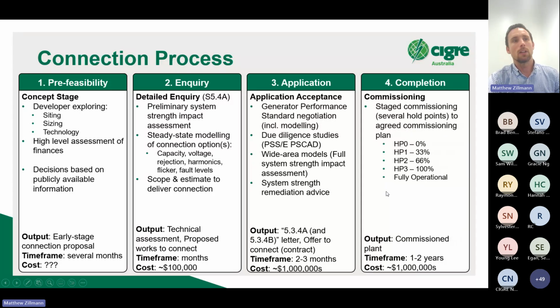The last bit I'd call out is once the system's built, you move into commissioning. It's extremely standard to have staged commissioning—using the example of a 100 megawatt generator connecting into a distribution network, you don't just say on day zero, 'go for it, you're commissioned, let's see how you go.' They'll work through staged hold points and release that capacity in stages.